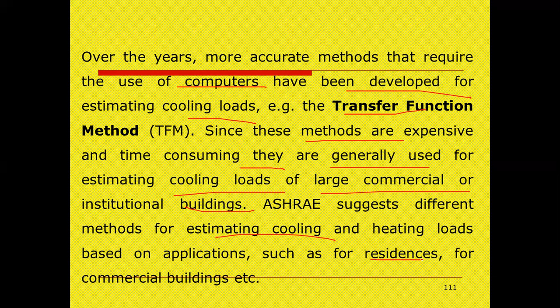Next, over the many years, more accurate methods that require the use of computers have been developed for estimating the cooling loads, for example the transfer function method, TFM. Since these methods are expensive and time consuming, they are generally used for estimating the cooling loads of large commercial and institutional buildings. ASHRAE suggests different methods for estimating the cooling and heating loads based upon the applications, meaning based upon the usage, such as residential, commercial, and industrial applications.